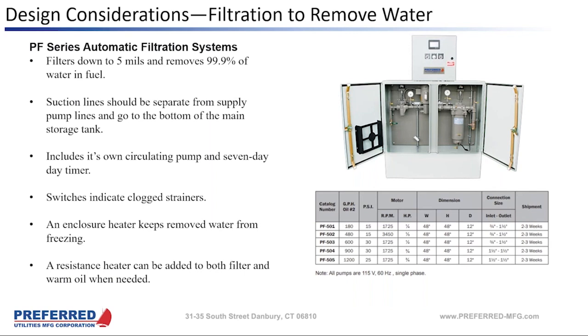One of the other considerations to keep in mind is that, right, we have a strainer on here, we have a circulation pump, we have all these things. We don't necessarily want those in line in our critical path to keep the generators running. I see that design every once in a while on drawings that we're asked to bid, where they'll show basically what we have inside this polisher between the supply pumps and day tanks or belly tanks. And we don't want that, because if you get a batch of bad fuel, or if your tank starts having a problem, if you clog up this filter, like Alex was saying, now you've cut off fuel to your gensets.